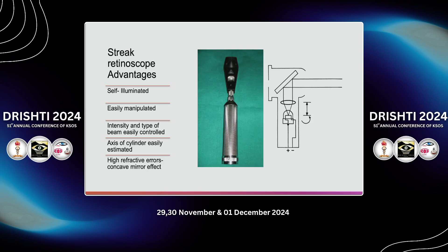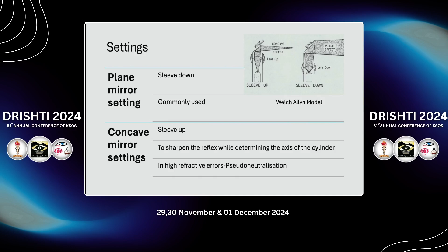So basically you have two settings: a plane mirror setting and a concave mirror setting. With the Welch Allyn model, when you pull the sleeve down, you have the plane mirror setting. That is commonly used. Very rarely you need to use the concave mirror setting. That is when the sleeve is up. It's usually used only if you want to find the axis of the cylinder and sharpen the reflex. With a plane mirror, you get a broader reflex. With a concave mirror, you get a thin streak. So it helps to find the axis of the cylinder. In high refractive errors, there's a thing called pseudo-neutralization. I'll explain that later.